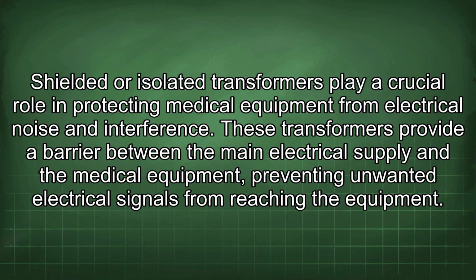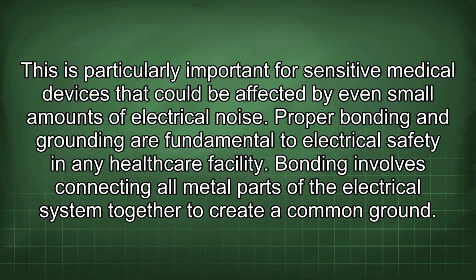Shielded or isolated transformers play a crucial role in protecting medical equipment from electrical noise and interference. These transformers provide a barrier between the main electrical supply and the medical equipment, preventing unwanted electrical signals from reaching the equipment. This is particularly important for sensitive medical devices that could be affected by even small amounts of electrical noise.